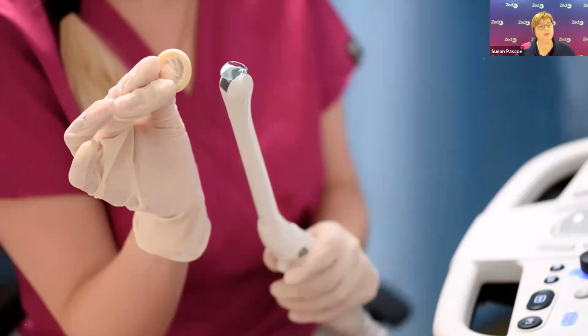And then we apply some gel to the face of the probe, and then whatever the probe cover that we're using, we put that over the top, and then some extra lubricant goes on the outside of the probe. We need an air-free transition from the probe face all the way to the patient's anatomy. So you just need to double check and make sure, run your finger over the end of the probe before you pop it in the vagina so that you can make sure there are no air bubbles. If you have an air bubble under your condom or under your probe cover, then there's no way of getting around taking out that probe and recovering and starting again. So just make sure that you smooth out any air bubbles before you pop the probe into the vagina.